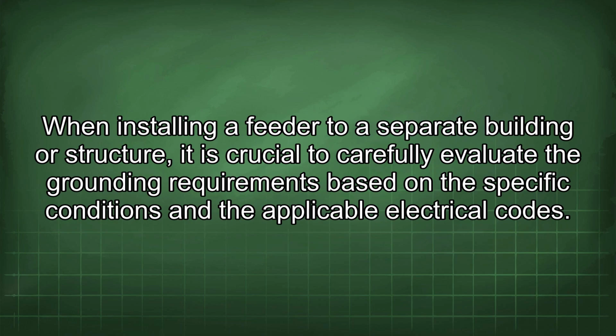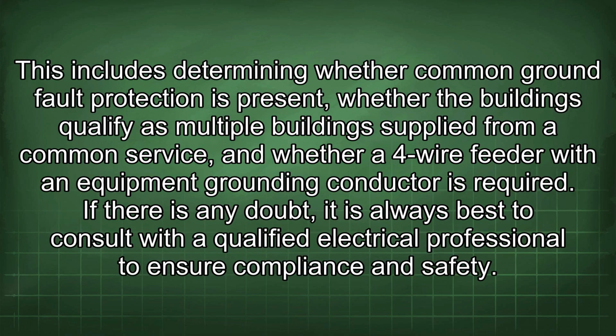When installing a feeder to a separate building or structure, it is crucial to carefully evaluate the grounding requirements based on the specific conditions and the applicable electrical codes. This includes determining whether common ground fault protection is present, whether the buildings qualify as multiple buildings supplied from a common service, and whether a 4-wire feeder with an equipment grounding conductor is required. If there is any doubt, it is always best to consult with a qualified electrical professional to ensure compliance and safety.